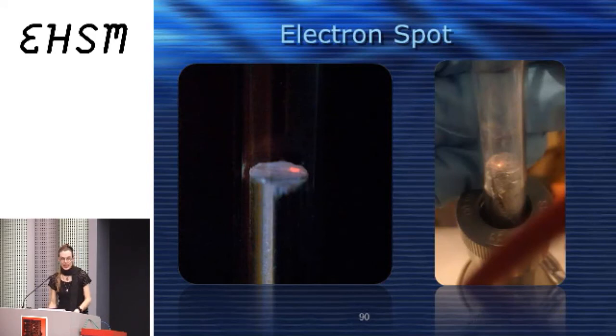And this is a single lens design, a very low precision lens. So by adding multiple lenses, you can demagnify the previous crossover. If this spot's 0.2 and you put another lens, you can demagnify that by another 10 times and get 0.02, and then you can put another lens in and demagnify that. And aberrations become introduced and become limiting, so you need quadrupoles and hexapoles to squish the beam back round.